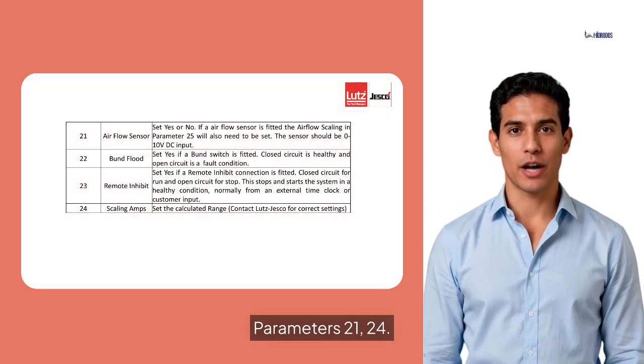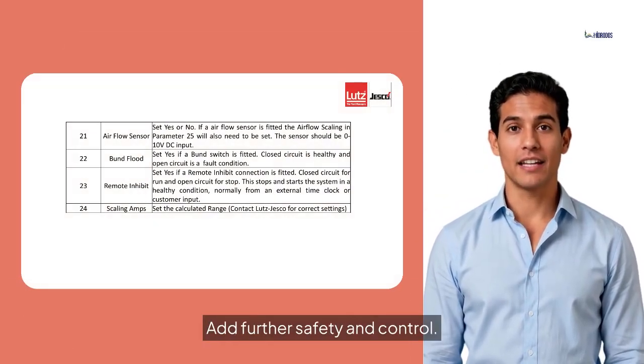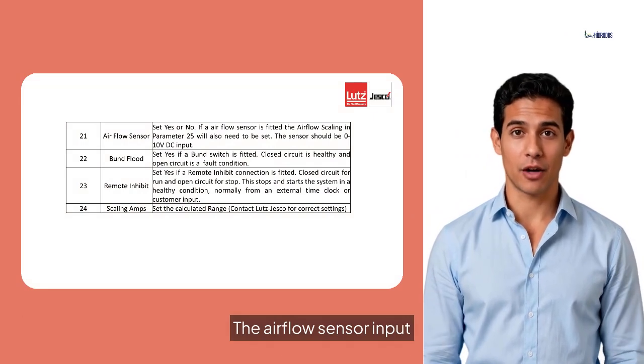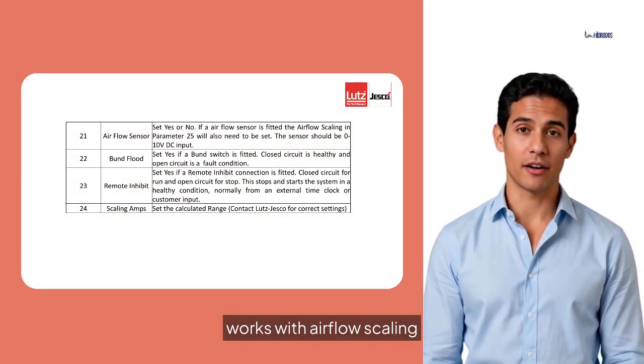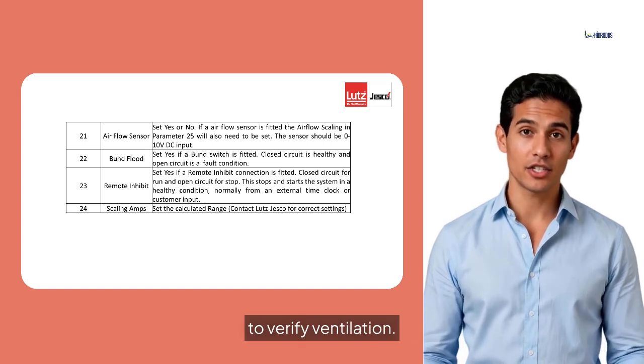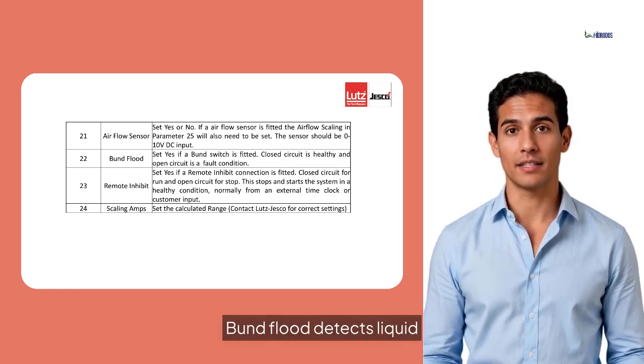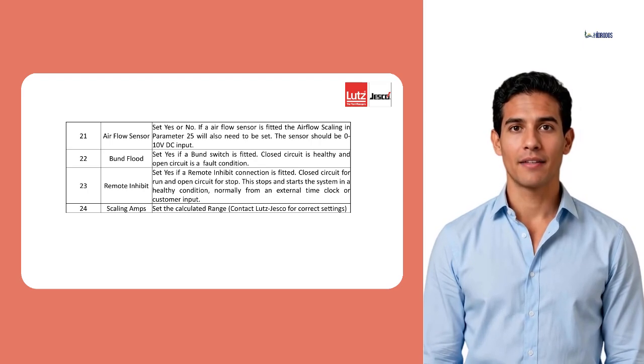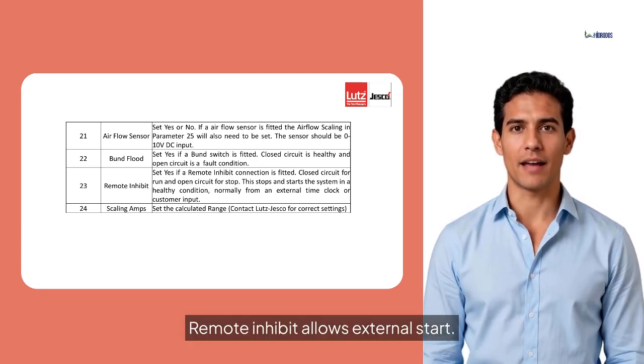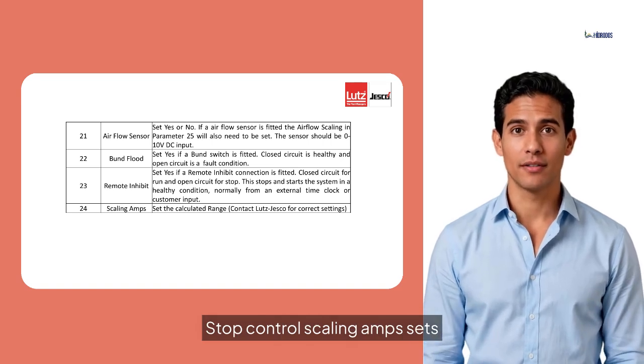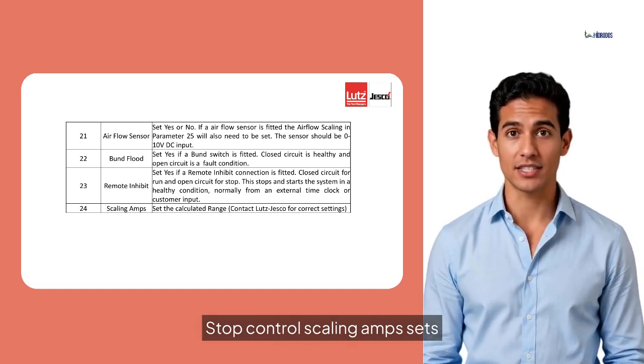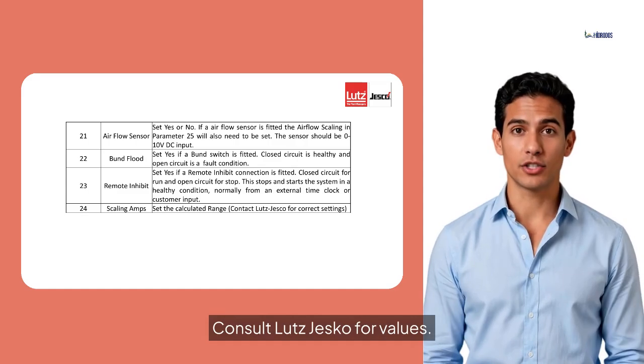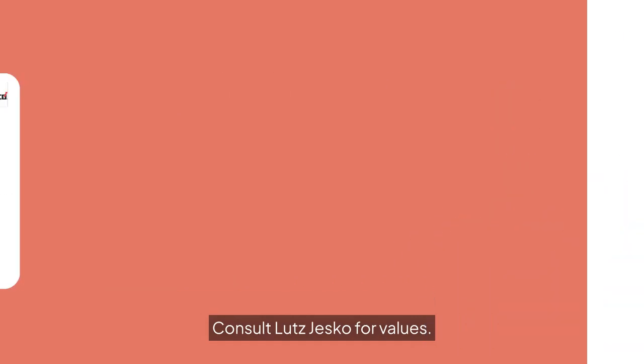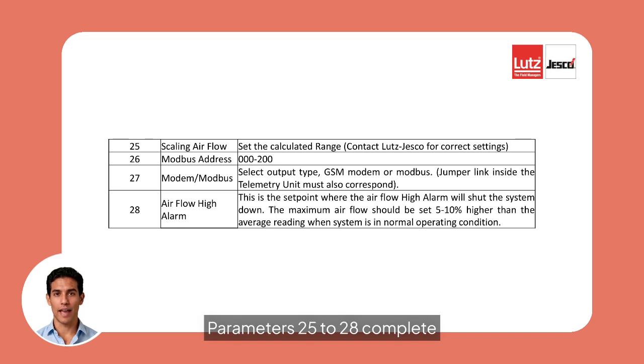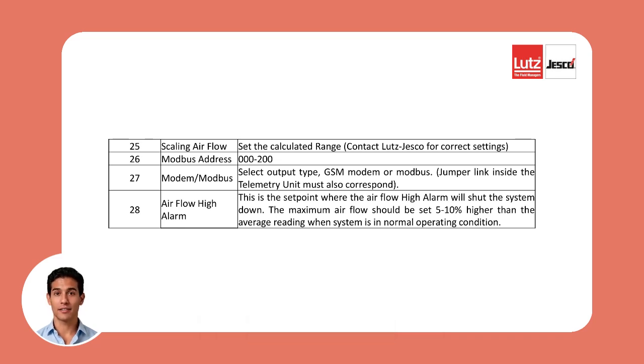Parameters 21 to 24 add further safety and control. The airflow sensor input works with airflow scaling to verify ventilation. Bund flood detects liquid in the bunded area. Remote inhibit allows external start-stop control. Scaling amps sets the correct current range. Consult Lutz-Jesco for values.